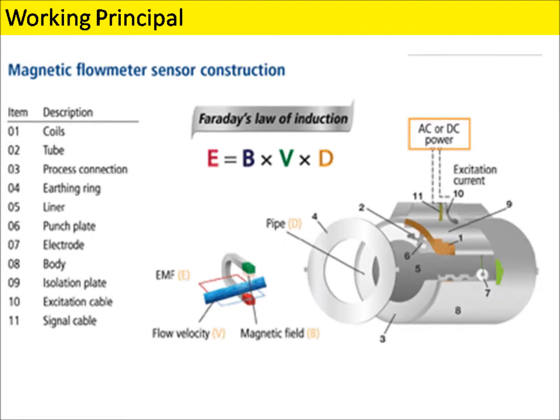Magnetic flow meter construction is very straightforward. The magnetic flux field, B, is generated by a coil that is mounted perpendicular to what are typically two electrodes. They will pick up the induced electromotive force, voltage. The magnetic field generates an electromotive force proportional to the magnetic flux density, B, the velocity of the conductor, V, and the diameter of the pipe, D.